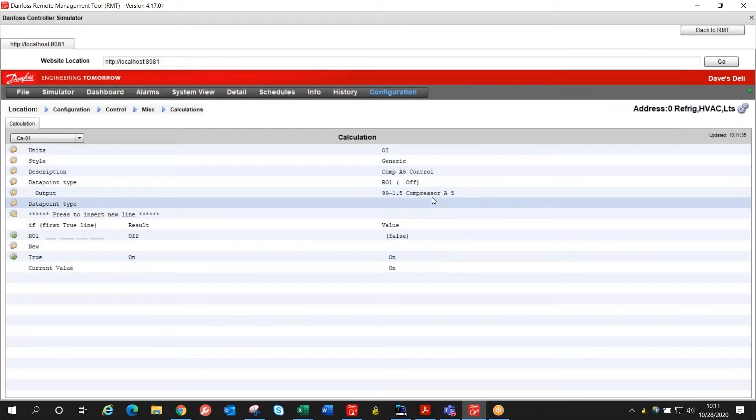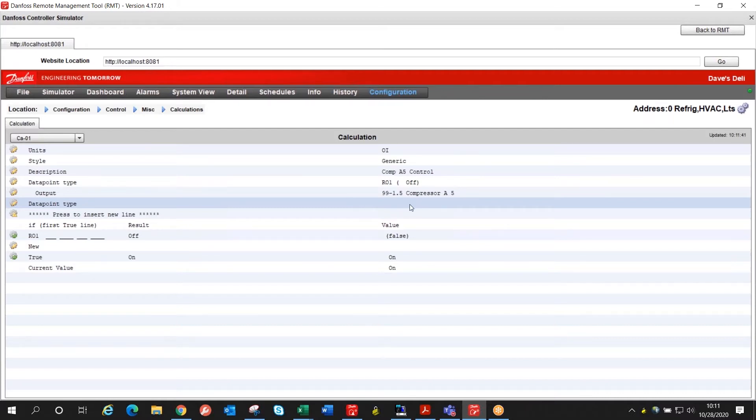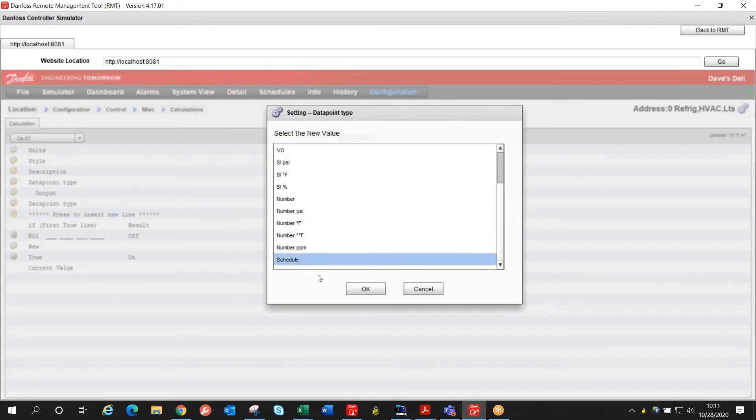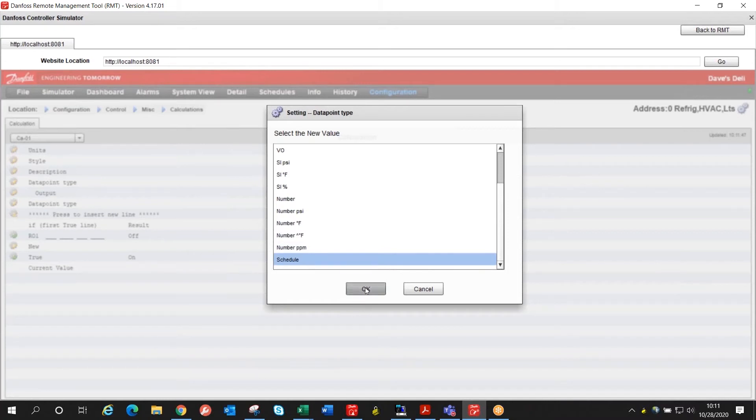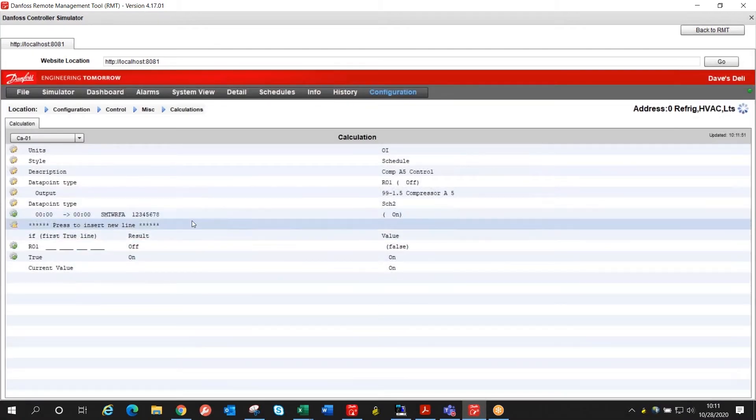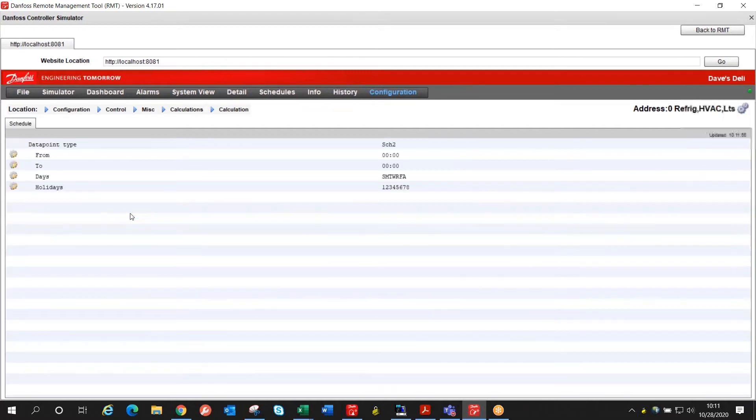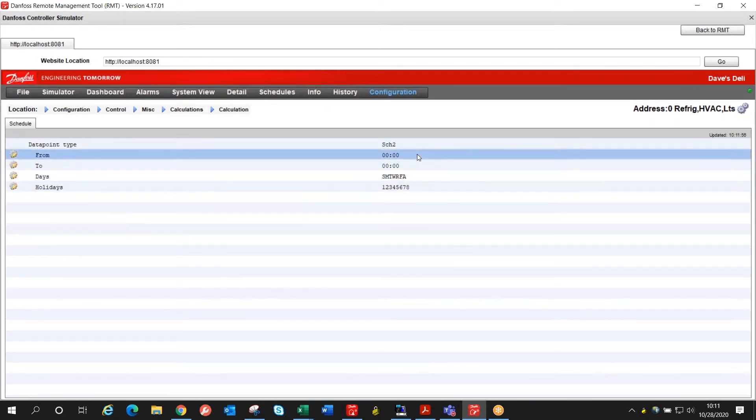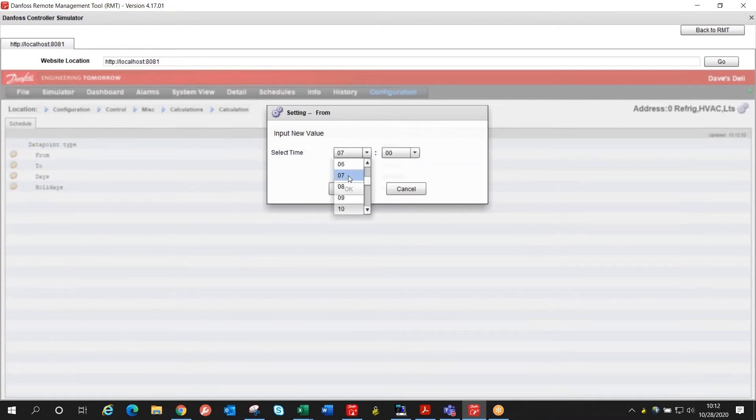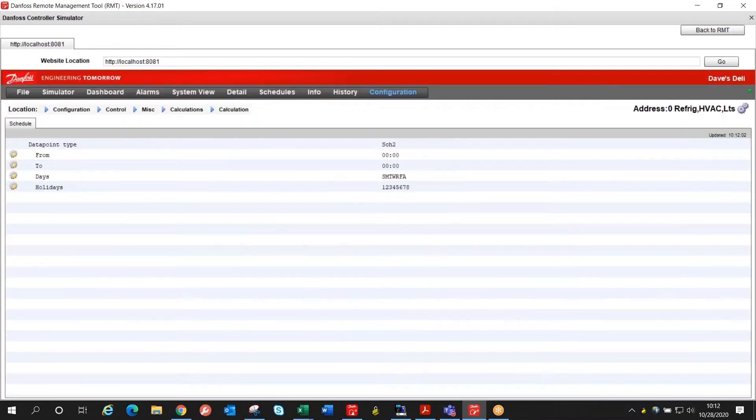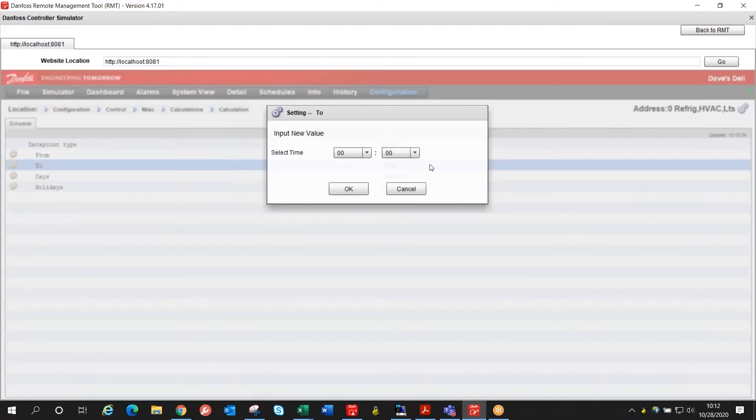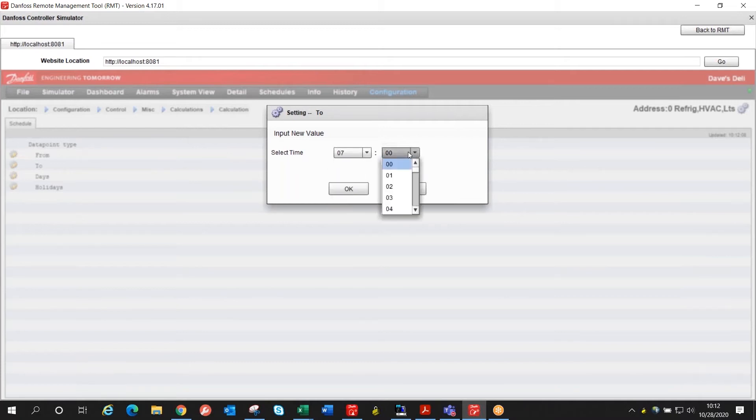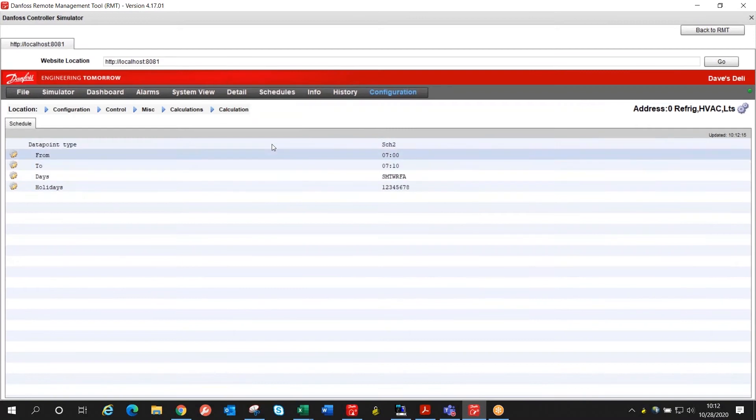So we've got our relay. Now we need to tell it when to run so we're going to add a schedule. We've got an empty data point here so we'll double click on that. Scroll down until we get to the schedule option. Now we've got a 24-7 schedule but we need to edit that. I'll double click on that. We're going to change this to run at 7 a.m. to start and we're going to let it run for 10 minutes so we will have the schedule from 7 to 7:10.